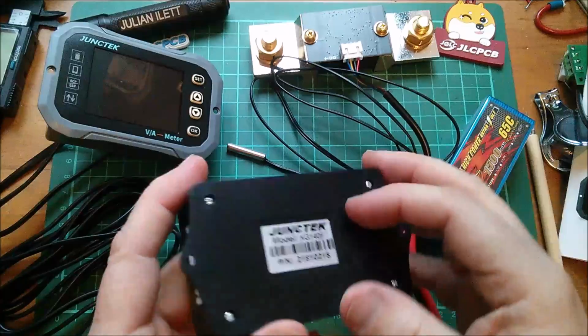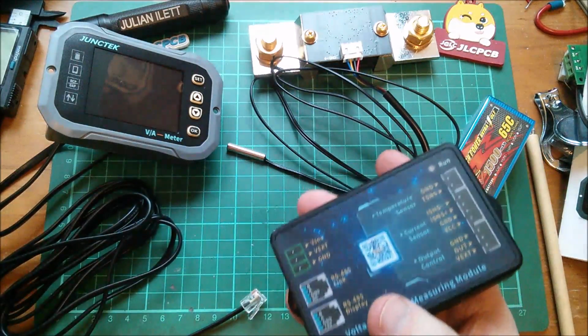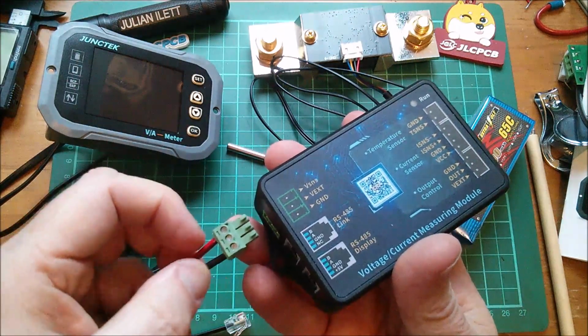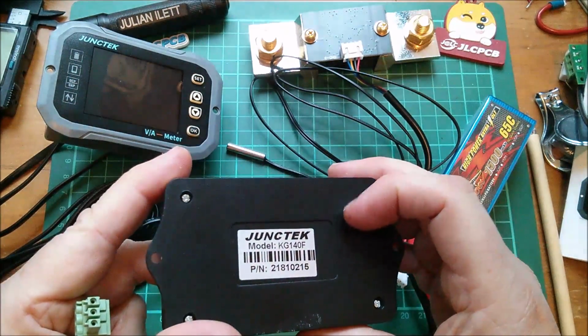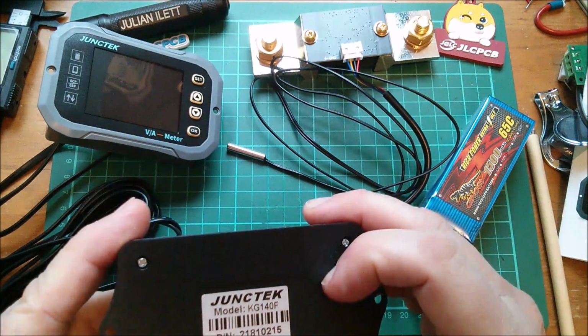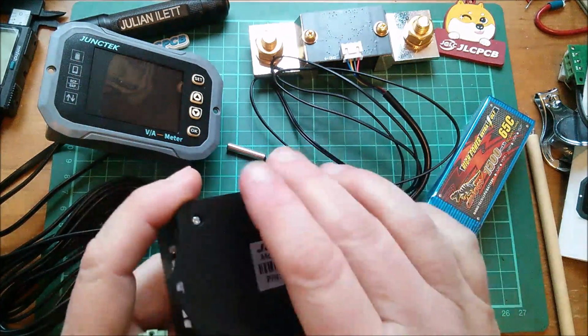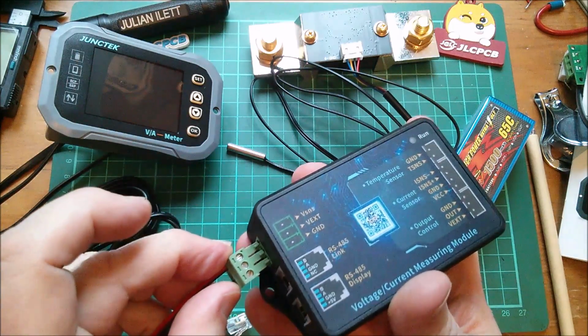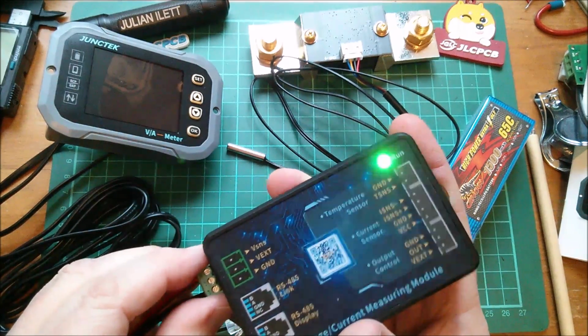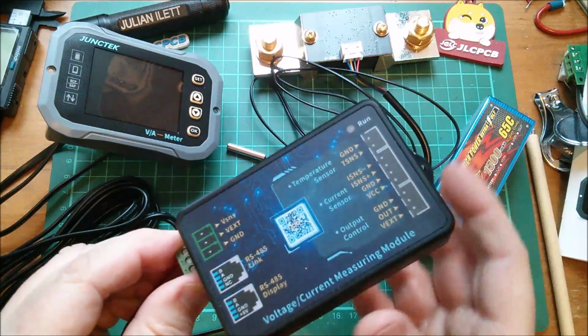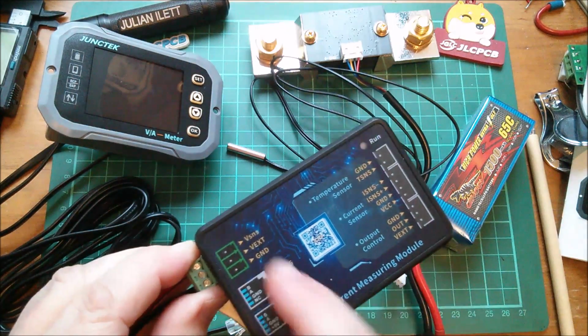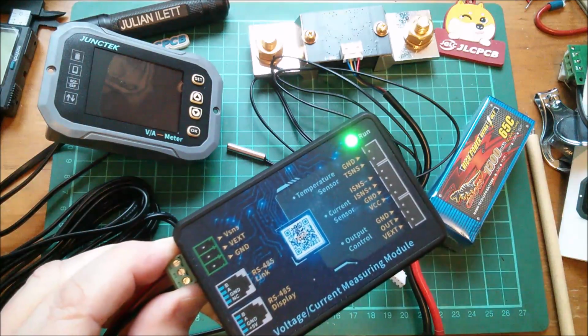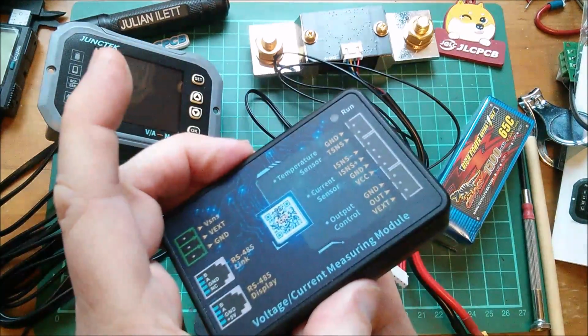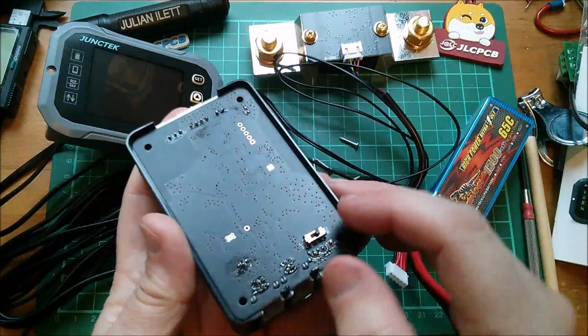Oh, that's the little switch for whether you're using the 2-wire powering method, which is what I did, just using V-Sense to actually power this. If you switch the little switch to 3-wire, I imagine, oh, it's quite deeply buried in there, I imagine it wouldn't power from V-Sense. It would require to put the V external in, so it probably just switches between V-Sense and V external to route power into the electronics inside here. Right, inside the electronics box, there's the little 2-wire and 3-wire switch.